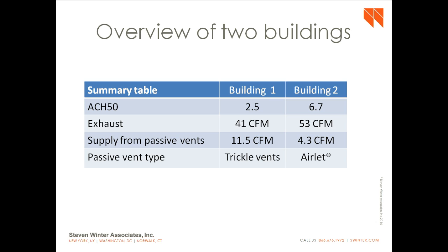the tighter apartment, the performance from the passive vents is a lot better from the building with airtight apartments than it is from the leaky apartments. So obviously airtightness has some effect on the ability for passive vents to draw fresh air in.